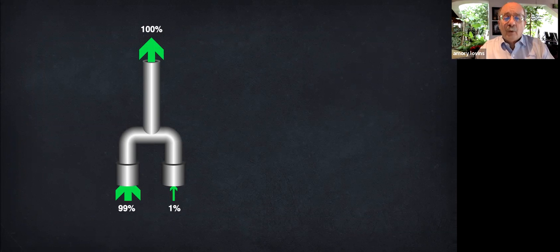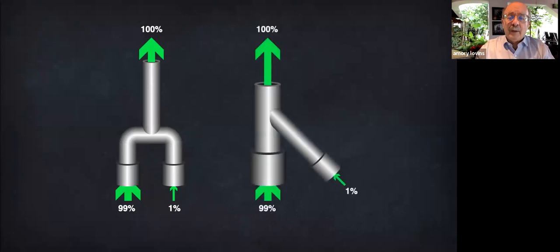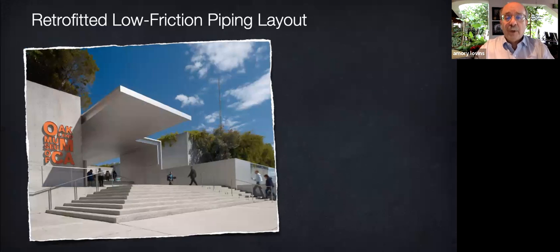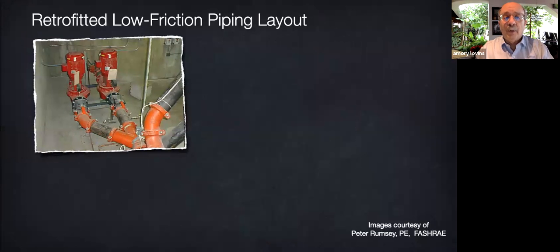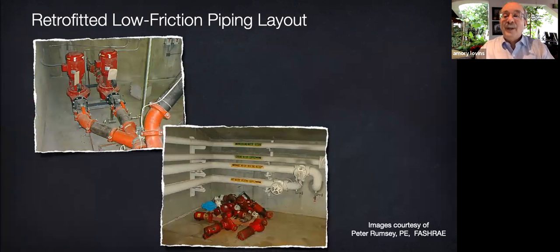For example, normally a critical pump with an in-place spare pump would be laid out like this, so the flow always goes through two right-angle bends. That means friction. Why not lay it out like this, so the main flow has no bends and also fewer valves? The same logic applies with identical pumps in tandem, a very common arrangement. At California's Oakland Museum, Peter Rumsey retrofitted an efficient layout into the condenser water pumping loop. And that cut the pumping energy by 3/4 with a 2 or 3 month payback, and it eliminated 15 pumps that will never again waste energy and maintenance costs.